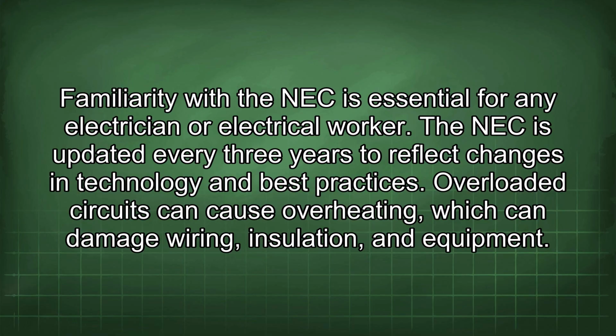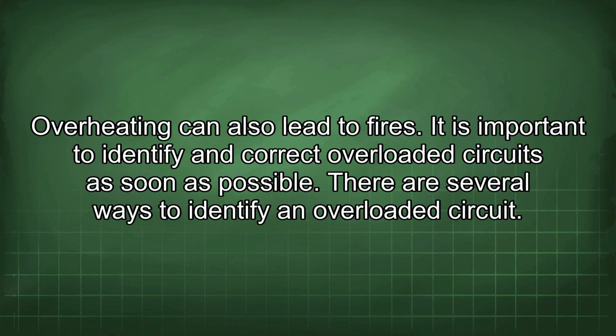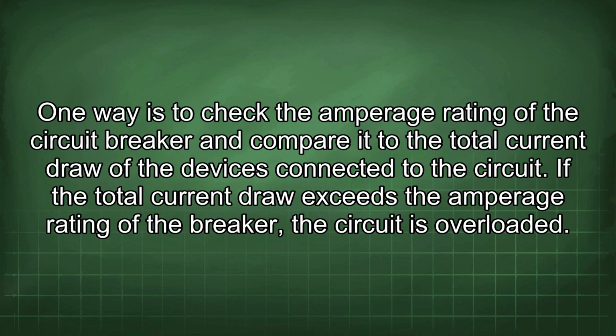Overloaded circuits can cause overheating, which can damage wiring, insulation, and equipment. Overheating can also lead to fires. It is important to identify and correct overloaded circuits as soon as possible. There are several ways to identify an overloaded circuit. One way is to check the amperage rating of the circuit breaker and compare it to the total current draw of the devices connected to the circuit. If the total current draw exceeds the amperage rating of the breaker, the circuit is overloaded.